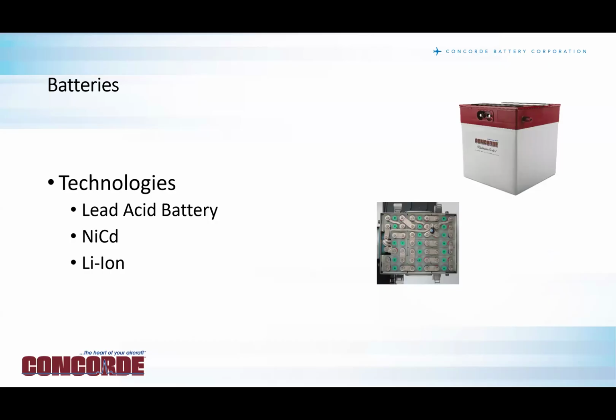And when I worked on that battery and I taught my technicians, I wanted them to treat that battery as 20 individual batteries within a can. Each cell has to be monitored. You have to take readings of each cell on discharge and charge. Add the right amount of distilled or deionized water, not tap water. Tap water will destroy the electrochemistry. So there's a lot of maintenance that's involved with a nickel cadmium, and I won't take much of your time because that's another 8 hours worth of discussion. So I just wanted to bring that point up to you.